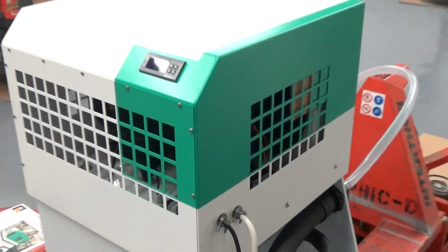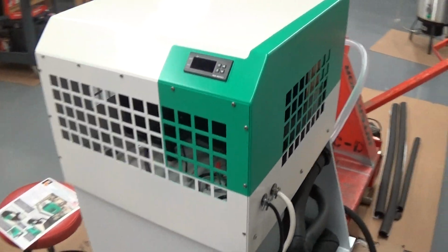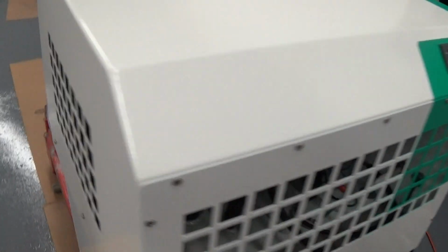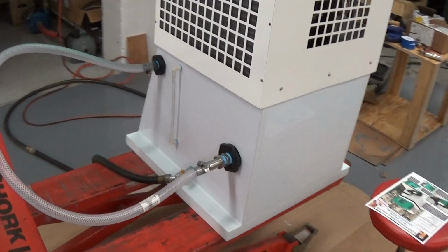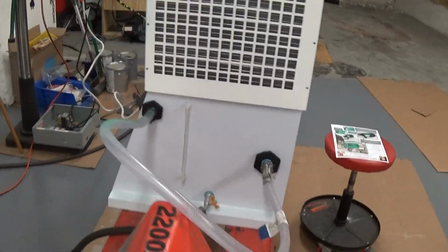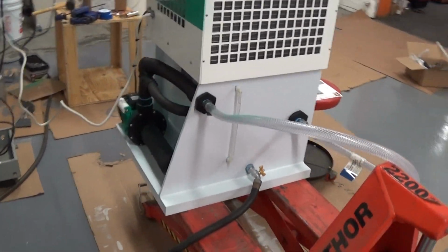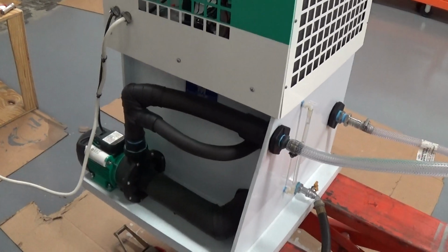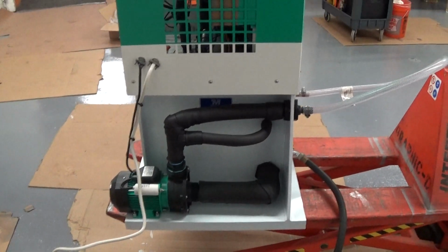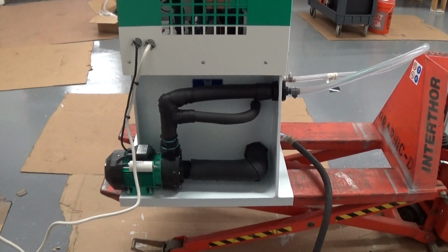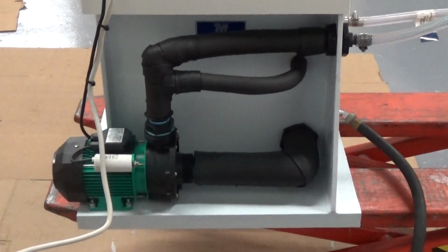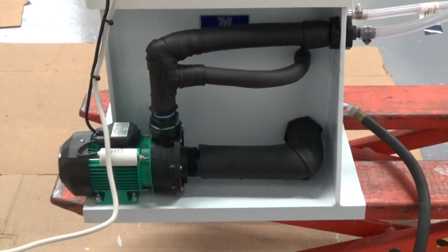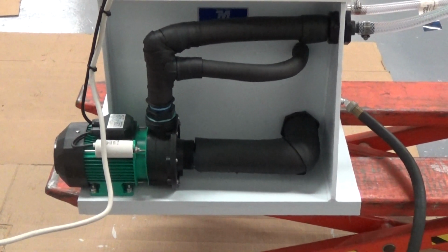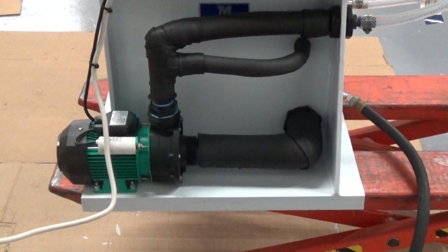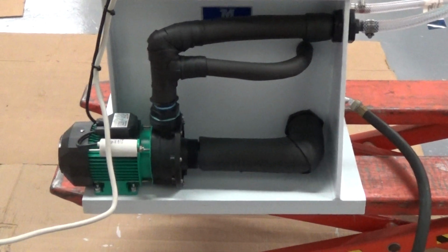So the top head, if you will, is where we have the compressor, condenser, and controls. The bottom is a heavy-duty poly rectangular tank with a very oversized heat exchanger intentionally. By that I mean that's an 18-gallon tank for a 1-ton chiller. That affords us some advantages, particularly in reducing the starts and stops on the compressor. The death of a compressor is when we have too many starts and stops. So it's been a nice fit, and the ones out in the field have been running fantastic.